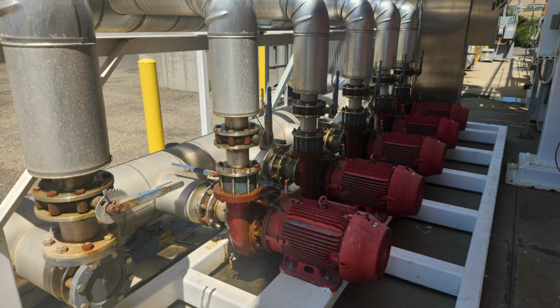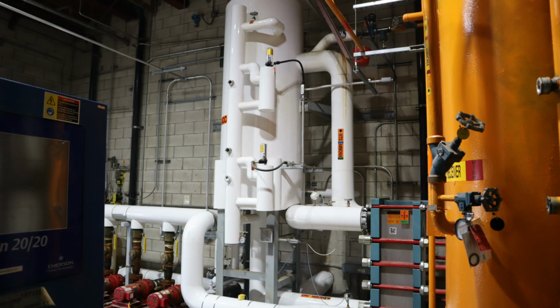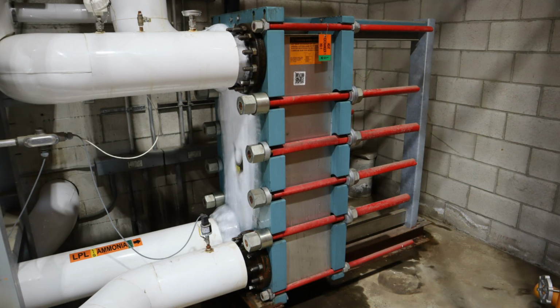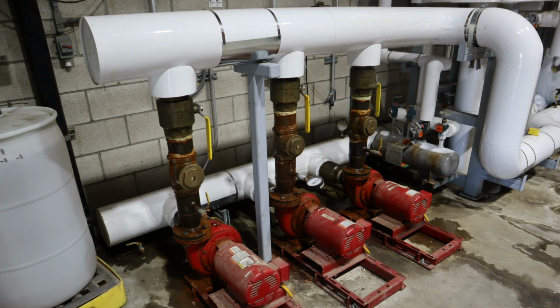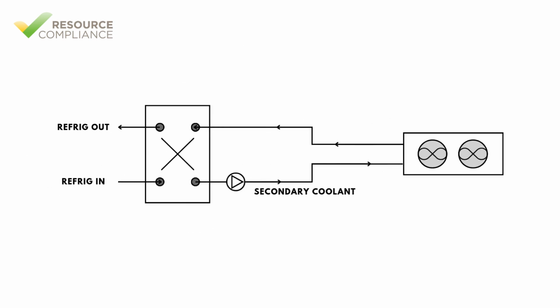In a refrigeration system using secondary coolants, the primary refrigerant absorbs heat from the secondary coolant in a heat exchanger. The secondary coolant, now cooled, is pumped through pipes or coils in the space or system that requires cooling. As the secondary coolant circulates, it absorbs heat from the environment or product being cooled and returns to the heat exchanger, where the cycle repeats.